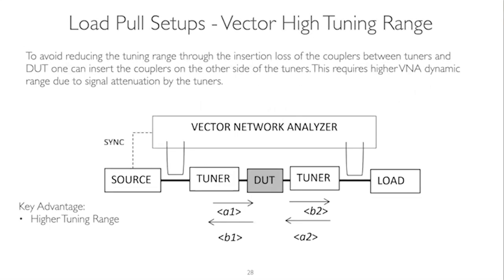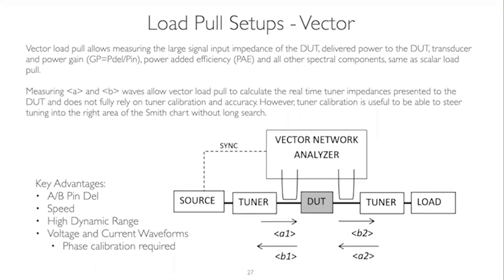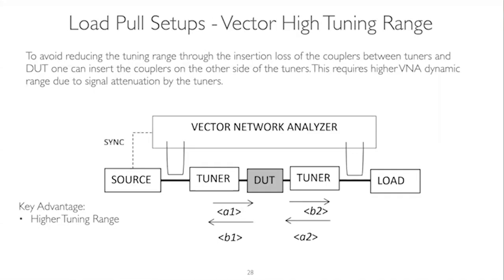Some customers will say, okay, that's fine, but when I go into this mode, you can see the couplers are between the tuner and the device. That creates additional loss, which minimizes the tuning range. So in some cases, we'll put the couplers outside the tuners, meaning before, not between the tuner and the device. They're basically outside, on the measuring side, after and before the tuner.